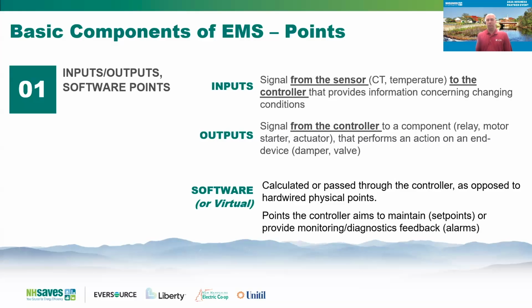That fan could be overridden at the VFD. The VFD could be in bypass. There could be a whole host of things that are going on. So it's really important to understand the difference between inputs and outputs. So again, inputs are from a sensor going into the controller. So it's the input to the controller. Outputs are signals going from the controller to either a relay, a motor starter, actuator, etc.